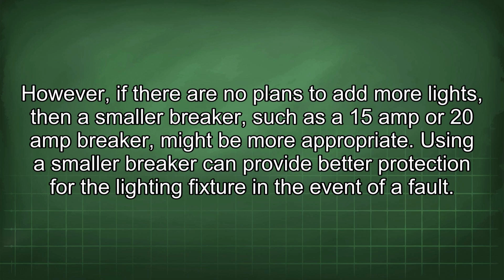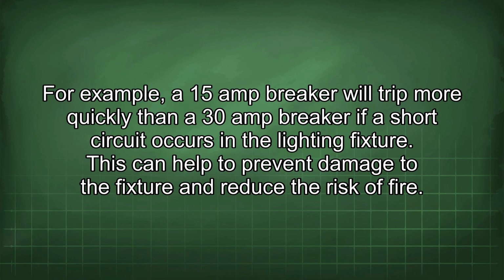Using a smaller breaker can provide better protection for the lighting fixture in the event of a fault. For example, a 15-amp breaker will trip more quickly than a 30-amp breaker if a short circuit occurs in the lighting fixture. This can help to prevent damage to the fixture and reduce the risk of fire.